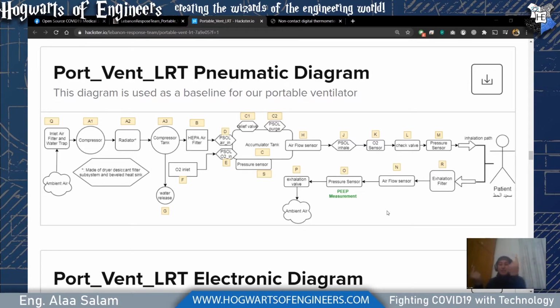And we have a set value. We compare these two values. We see, is there an acceptable margin of error? There's always some sort of leak happening somewhere. So your volume will be lost somewhere there. And also you have the air inside the breathing circuit, which is also there and stays there. This is why we call it dead space volume. So the sum of these volumes, are they equal to the tidal volume that we placed? If no, this is where the ventilator sees, I might have a leak somewhere, and it raises the alarm, leakage. And you go look for it.